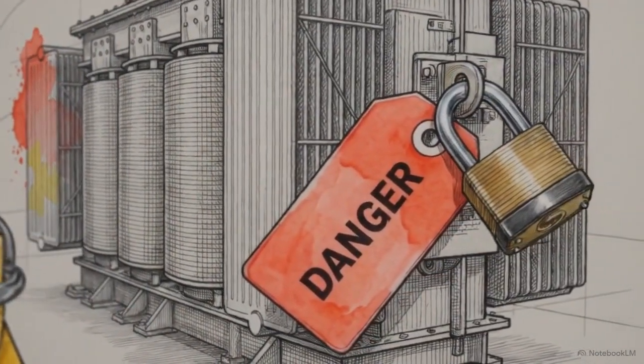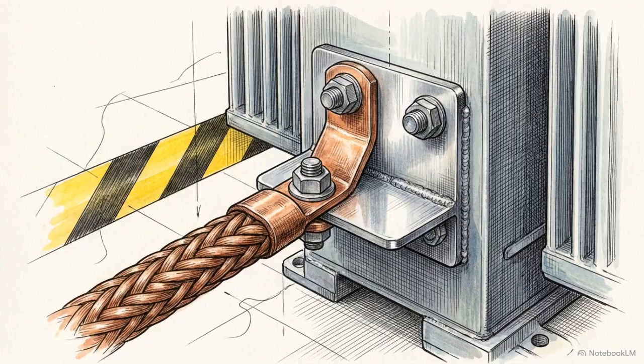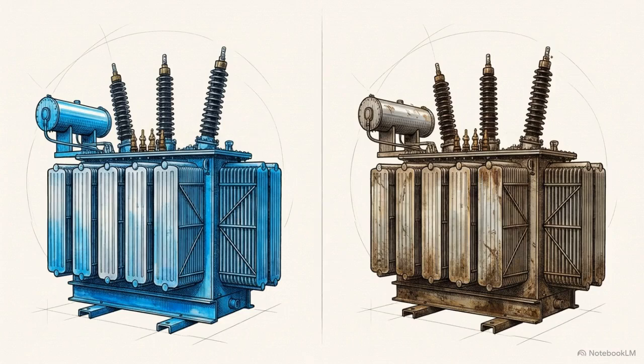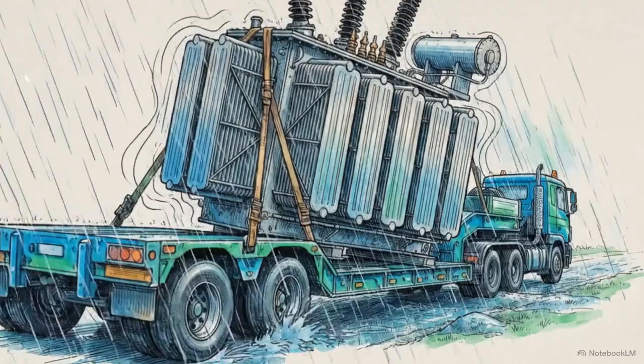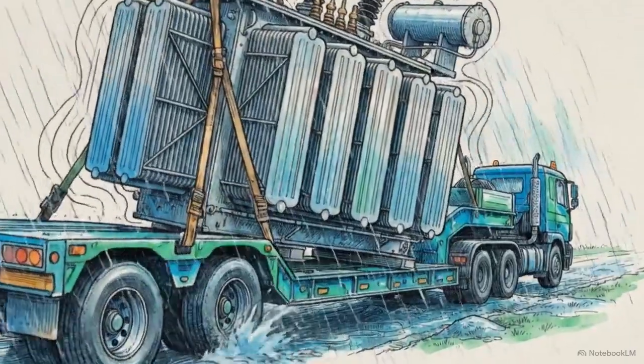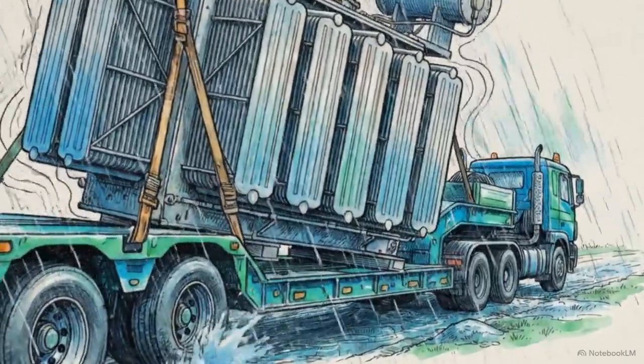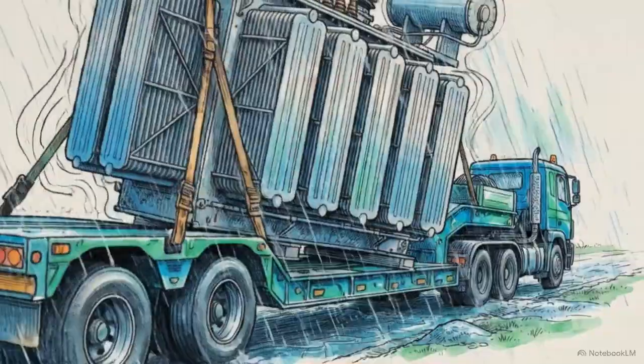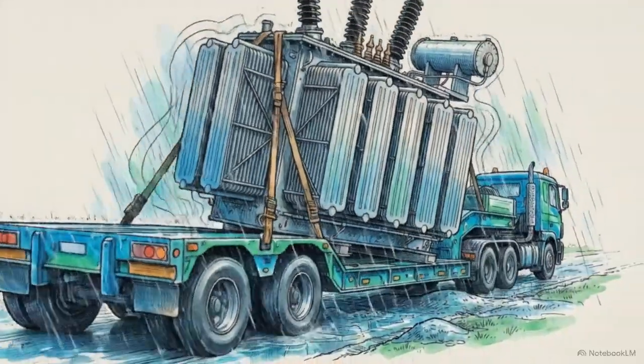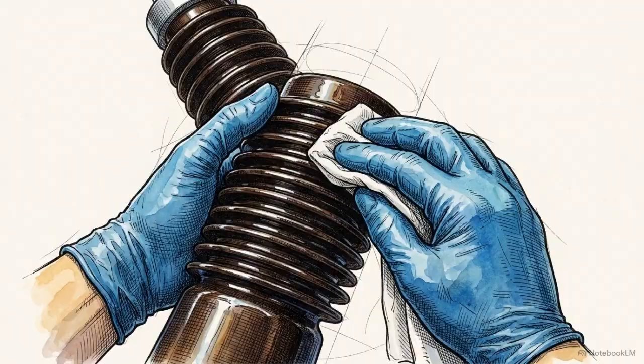This means strict physical isolation, verified grounding, and barricaded lockout-tagout boundaries around the entire asset. We do this because the objective is to validate the factory design against the field reality. A transformer may pass every inspection on the assembly line, but transit vibrations, moisture ingress, and installation handling can compromise its internal geometry. Part of establishing that baseline is physical preparation.